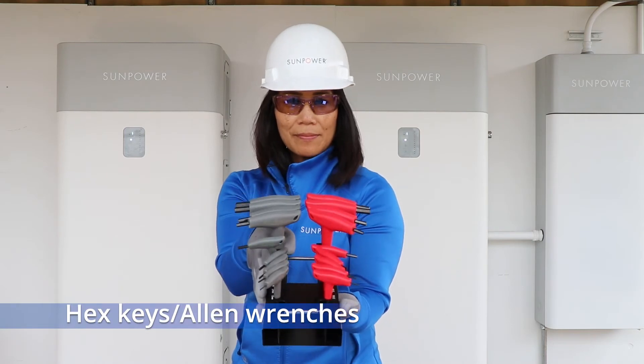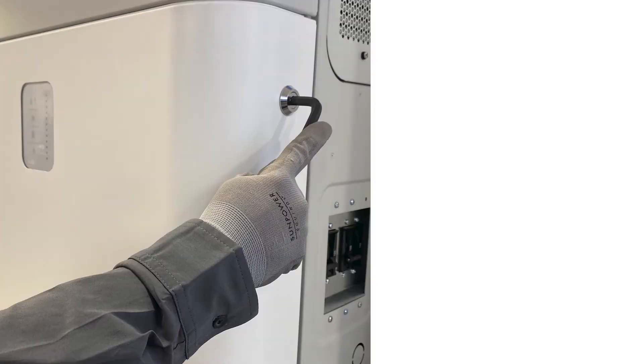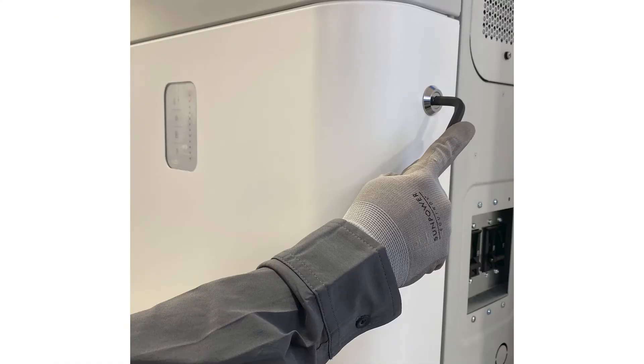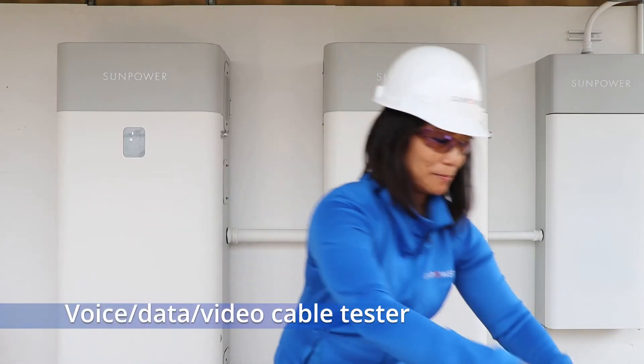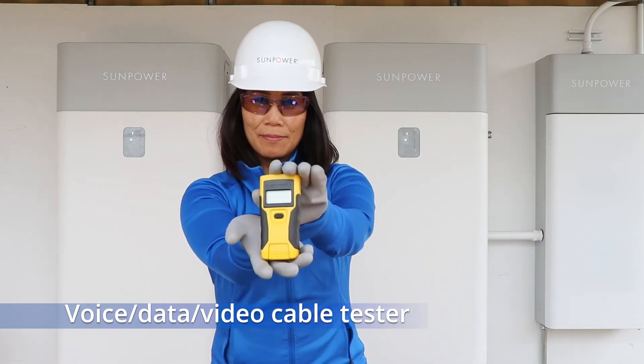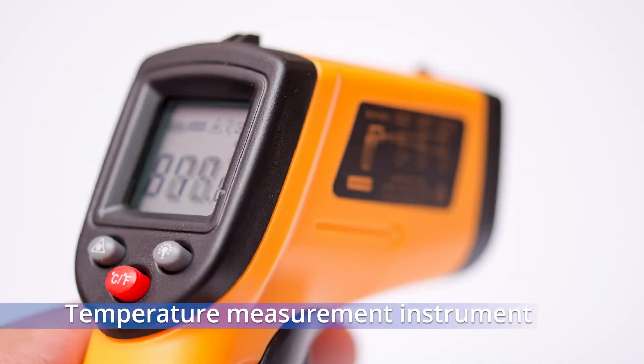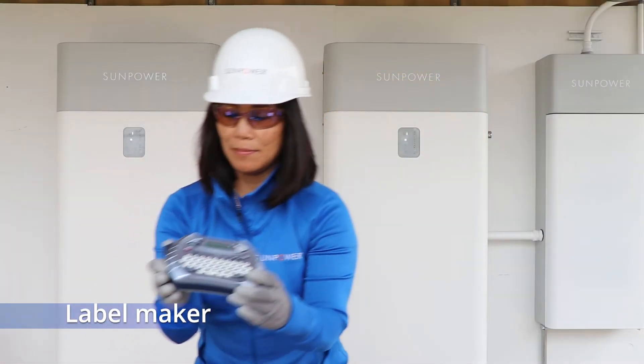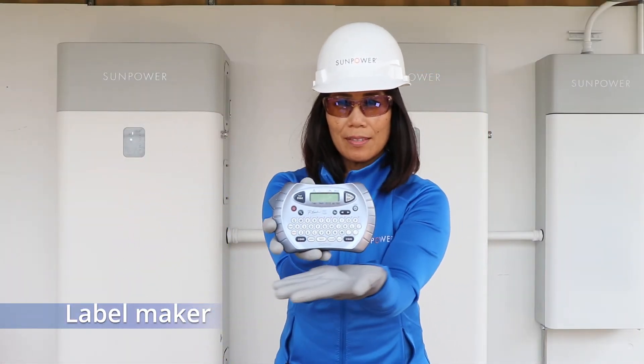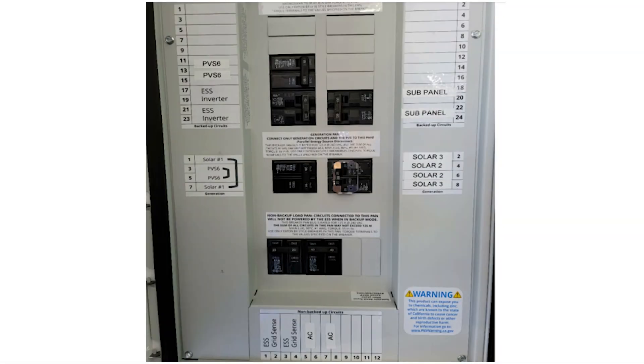You should already have a set of hex keys or allen wrenches, but make sure it includes a 5-16th allen wrench to open the ESS door latch. A voice data video cable tester is used to check communication cables and continuity. It's a good idea to have a temperature measurement instrument to measure the battery heat output. Lastly, you'll need a label maker for printing 3 quarter inch labels to indicate the migrated circuits on the Hub Plus dead front and other sub panels in the house.